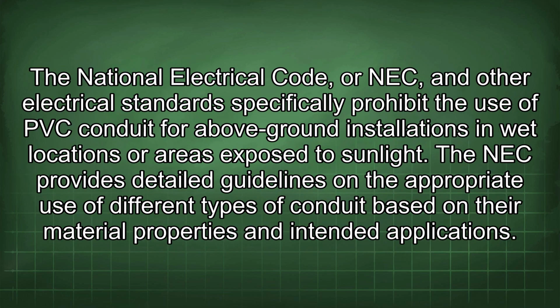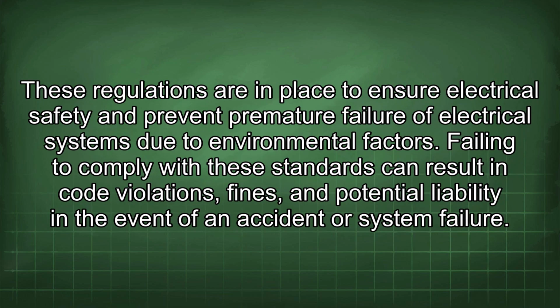The National Electrical Code, or NEC, and other electrical standards specifically prohibit the use of PVC conduit for above-ground installations in wet locations or areas exposed to sunlight. The NEC provides detailed guidelines on the appropriate use of different types of conduit based on their material properties and intended applications. These regulations are in place to ensure electrical safety and prevent premature failure of electrical systems due to environmental factors. Failing to comply with these standards can result in code violations, fines, and potential liability in the event of an accident or system failure.